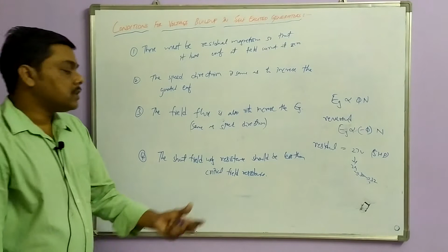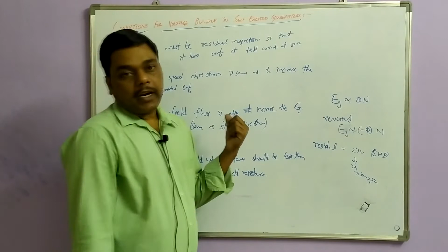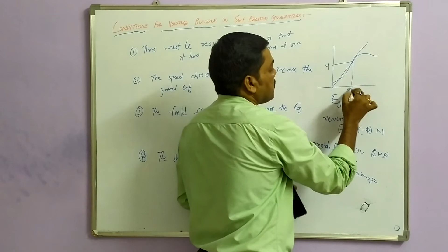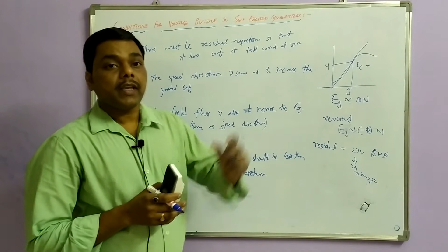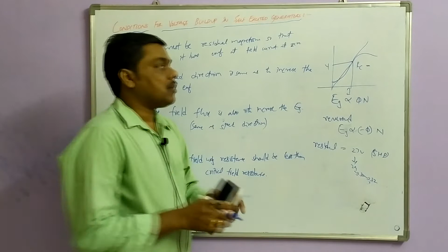Critical field resistance. So critical field resistance is the maximum value of resistance. Beyond that, the generator may not induce the EMF. We already drew this here. Suppose this is the OCC. Now this is the intersecting point. Where you are getting the maximum value of resistance of the shunt field winding, you can call it the critical resistance. It is the maximum value of field resistance. Beyond that, this curve may not intersect, so there is no induced EMF. That's why your shunt field winding resistance should be less than the critical field winding resistance.